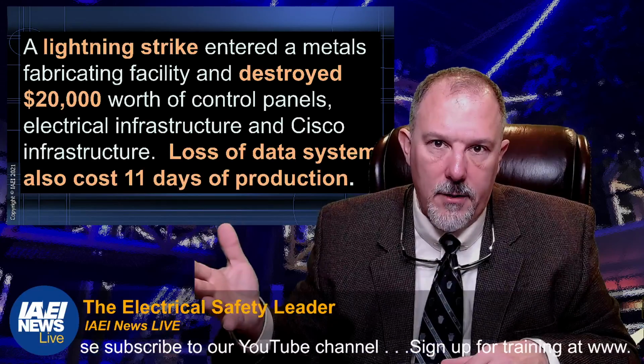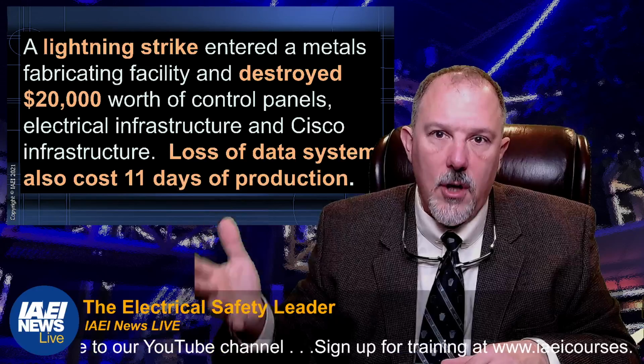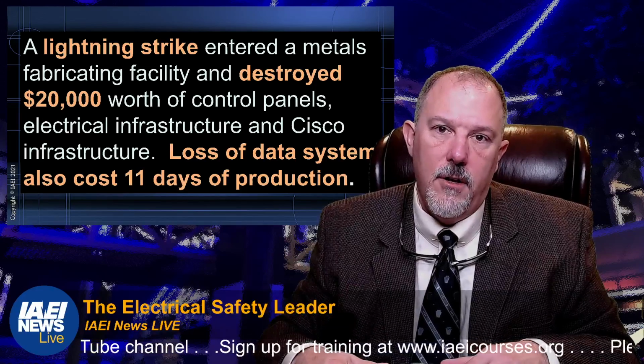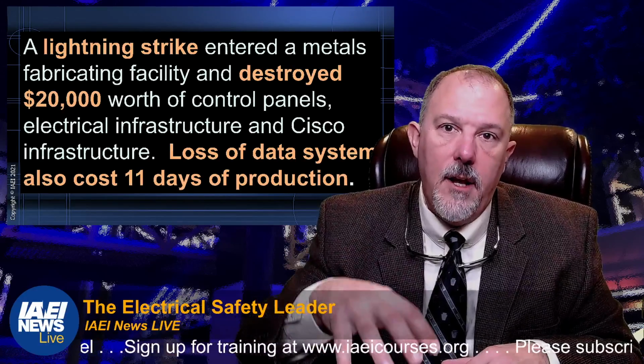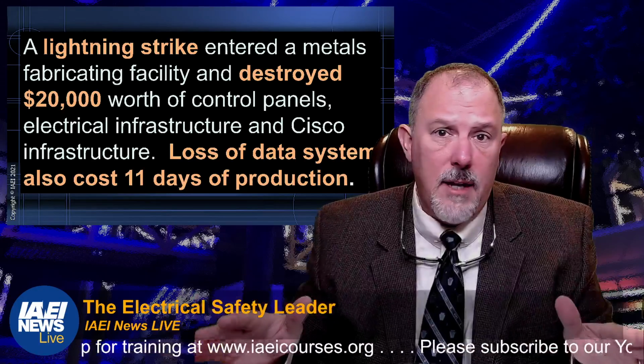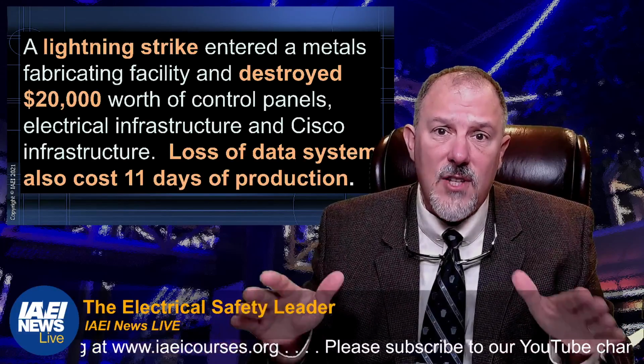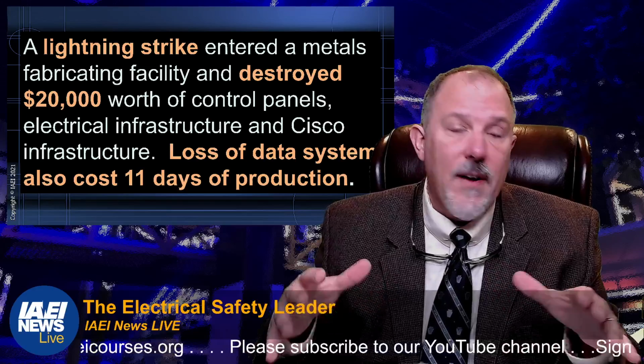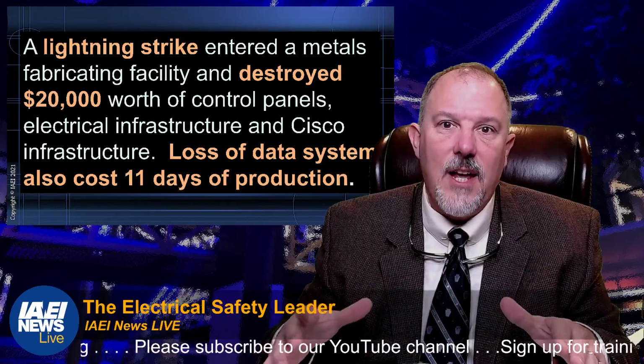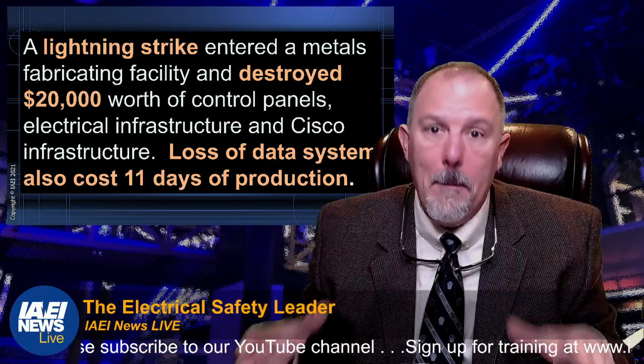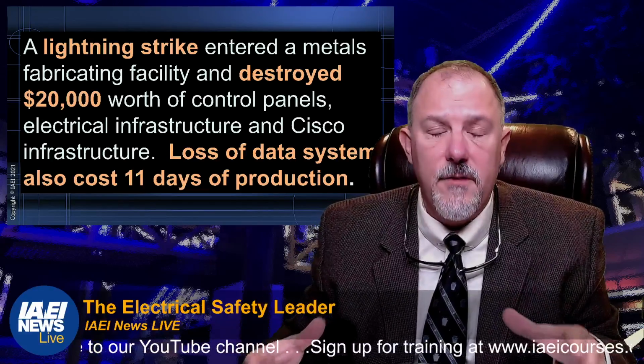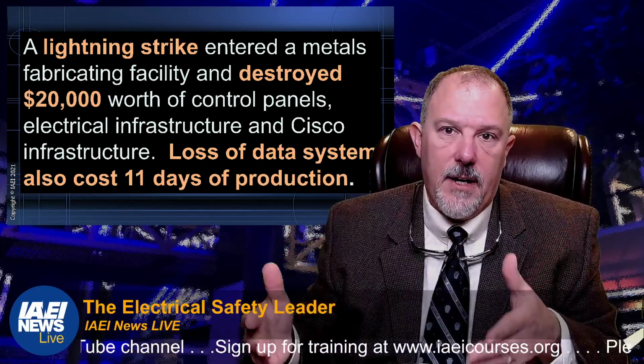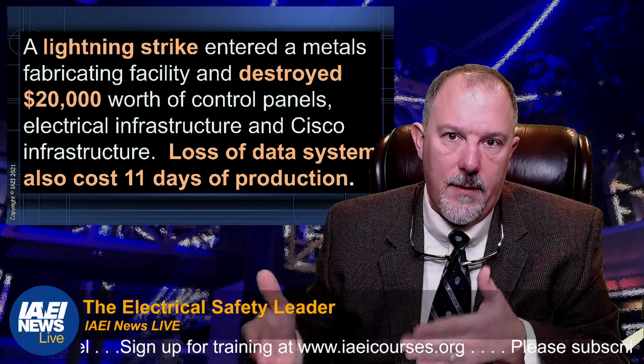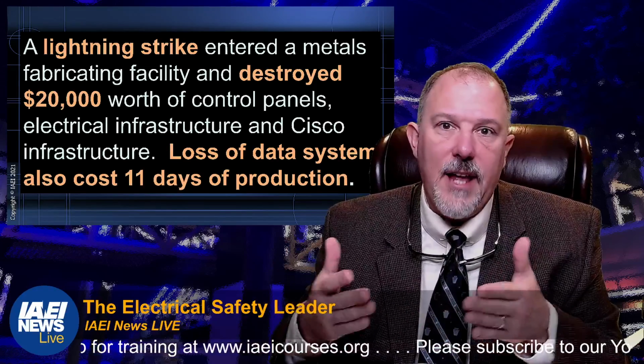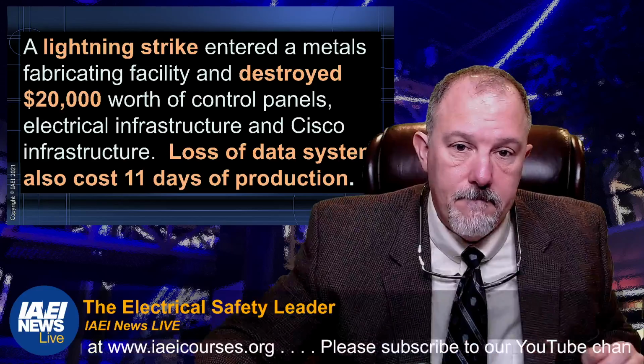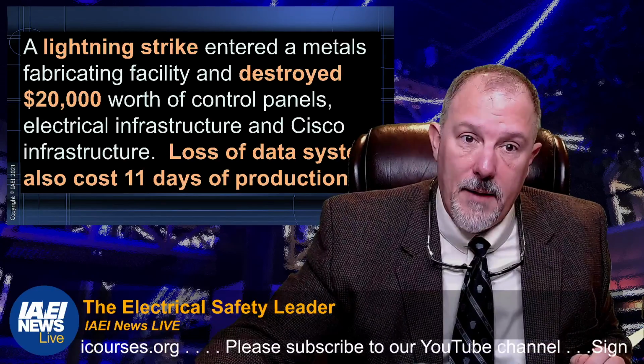millions and millions of dollars of loss due to surge, that is a justification for putting a surge requirement in the code. And it doesn't have to have a daggone thing to do with saving a life. If I can save our industry, if I can save across the United States, all homeowners combined, billions of dollars by putting surge protective devices in, I have justified the existence of surge in the National Electrical Code. Doesn't just have to be life safety. Persons and property. Don't forget about that.